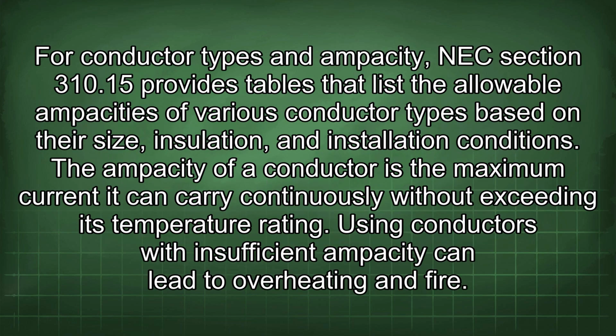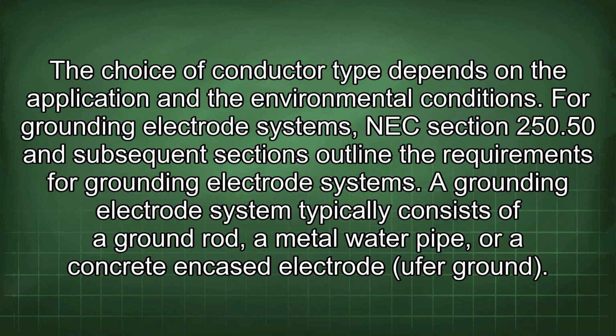For conductor types and ampacity, NEC section 310.15 provides tables that list the allowable ampacities of various conductor types based on their size, insulation, and installation conditions. The ampacity of a conductor is the maximum current it can carry continuously without exceeding its temperature rating. Using conductors with insufficient ampacity can lead to overheating and fire. The choice of conductor type depends on the application and the environmental conditions.